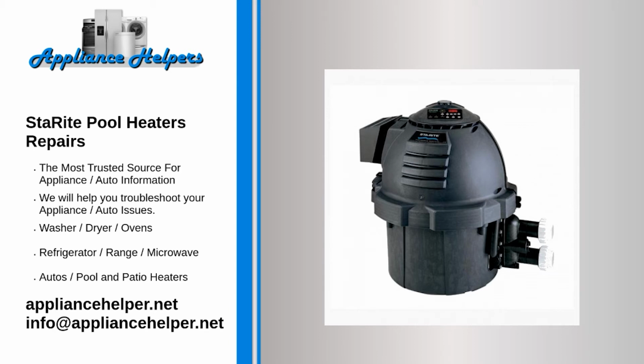Gas pool heater won't ignite. If the gas pool heater pilot light won't ignite, there are a few reasons for this. It's something that can be checked easily, but if the problem isn't visible, you may need to call a service professional to inspect further. Ensure that there is gas getting to the heater. Low gas pressure or no gas can be caused by a closed gas line supply valve, obstructed gas line, or an empty propane supply tank.